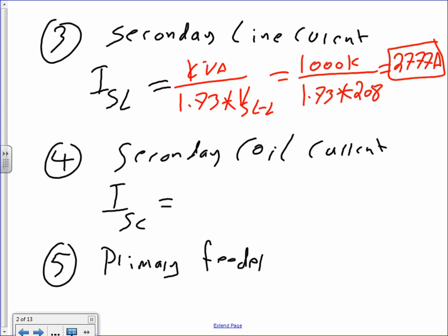2777, three sevens. What a number, huh? Did we do the math right though? Slightly, give or take 8. We're not going to fight over an amp on a system that's 3000 amps. Yep, you did the ratio. You could do the voltage ratio too and find it.